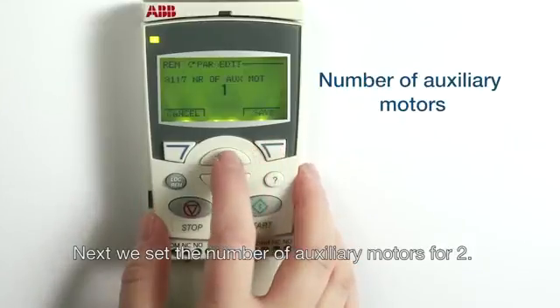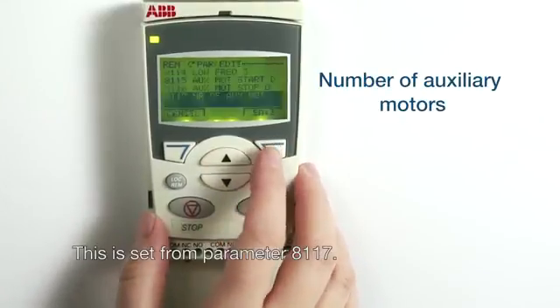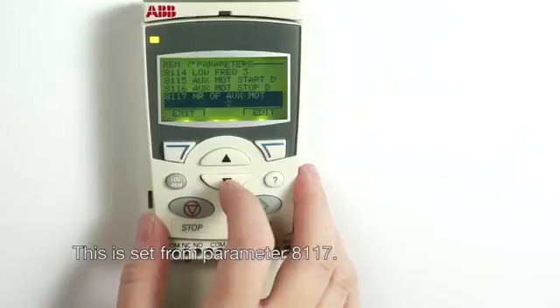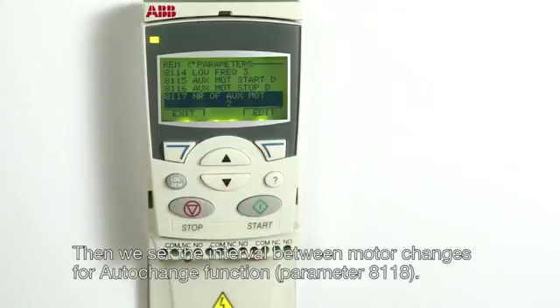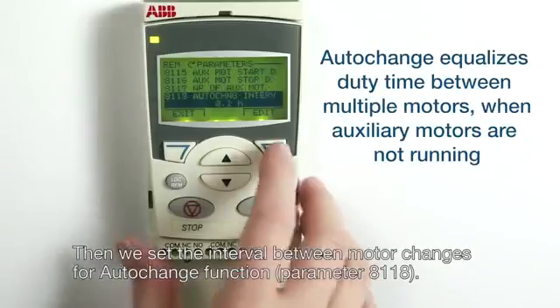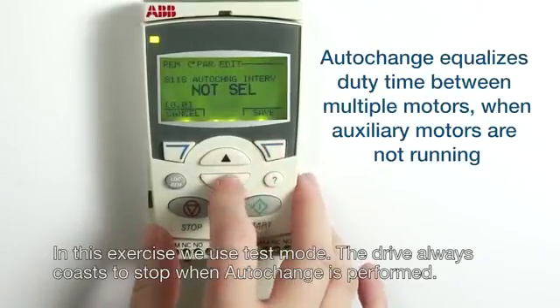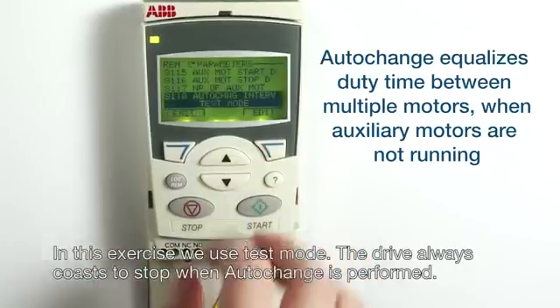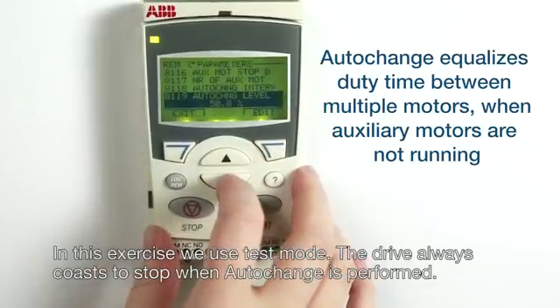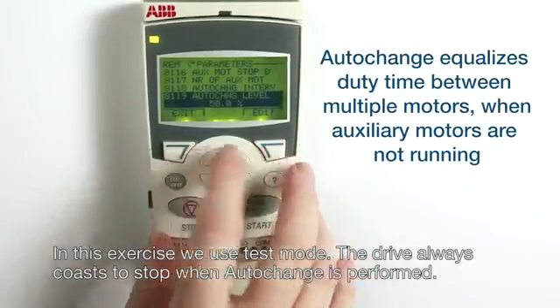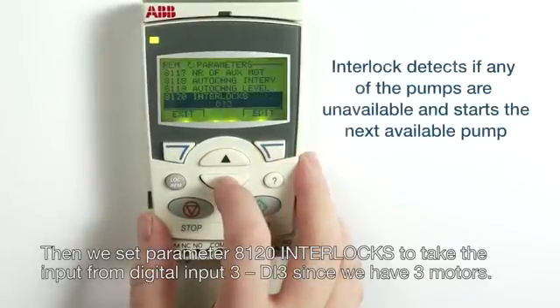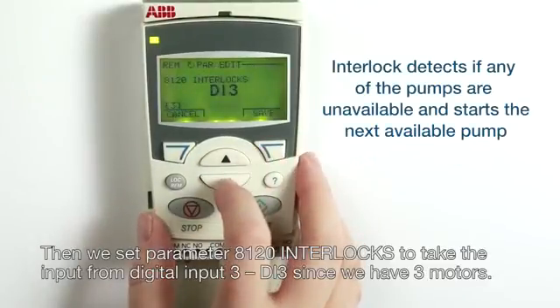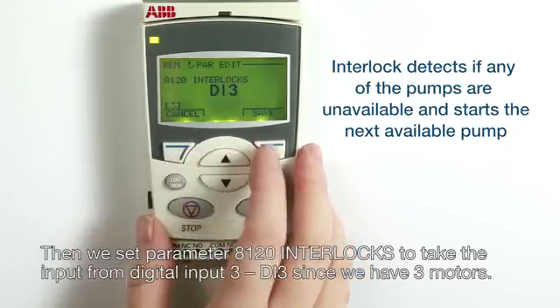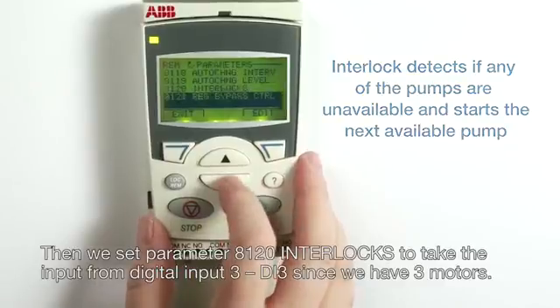Next we set the number of auxiliary motors to 2. This is set from parameter 8117. Then we set the interval between motor changes for the auto change function, parameter 8118. In this exercise we use test mode. The drive always coasts to stop when auto change is performed. Then we set parameter 8120 interlocks to take the input from digital input 3, DI3, since we have 3 motors.